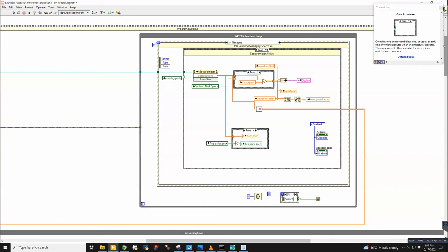There's always some sort of checking that you need to do between the two loops. Sometimes it's an LED that you use to make sure you're synchronized between the producing and consuming loop. There's a bunch of different ways to do it. So if it's checked by the number of spectra, and it's too fast and generates the same spectra twice, which is not correct, this counting catches it. If it is acquiring spectra slower than it's saving them, then you'll have the same spectrum twice in a row.